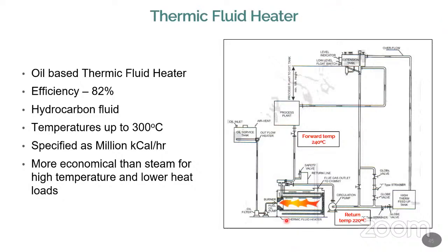Now you can see the system, which is again a closed chamber. We have a burner and the fuel is oil, something similar to furnace oil. We use this oil to heat up, and the heated oil flows through the piping system at very high temperature and goes to the process plant and all the areas. When the heat is transferred to the process, it cools, and then it comes back and is used again for our regular application.